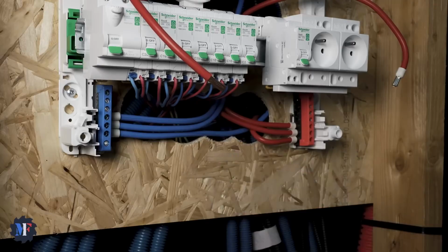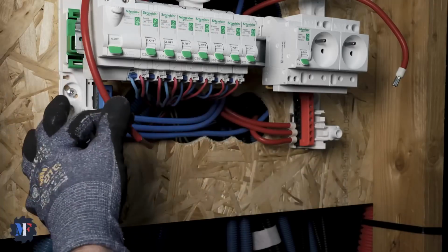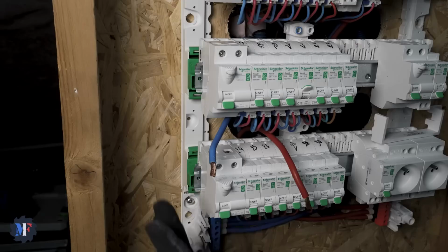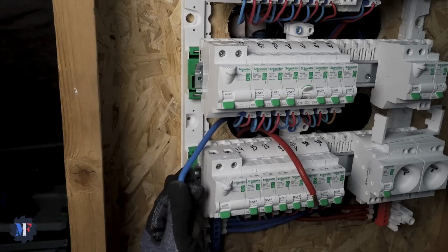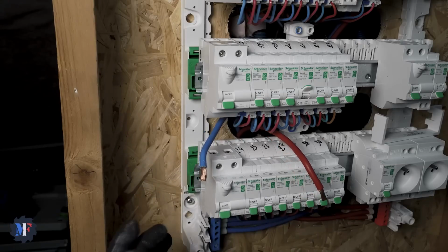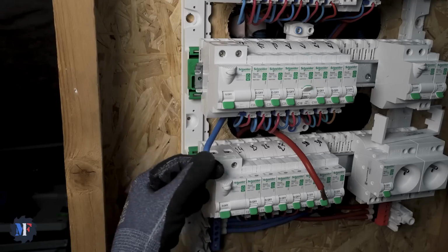Now we're going to connect the first differential breaker with the bus bars. So here we're going to power the first differential switch. I have the first one at the bottom since both my terminal block and 16mm2 are there, but it could also be at the top. I explained it to you. You can put the terminal blocks wherever you want.